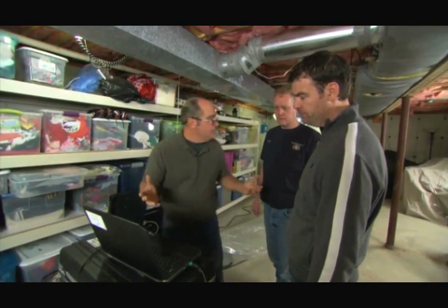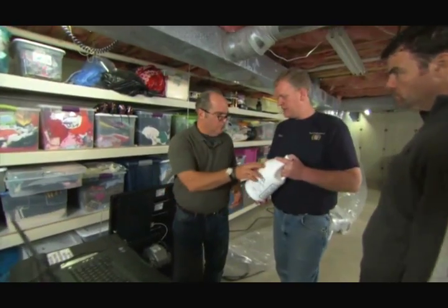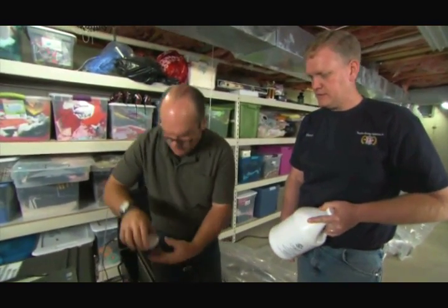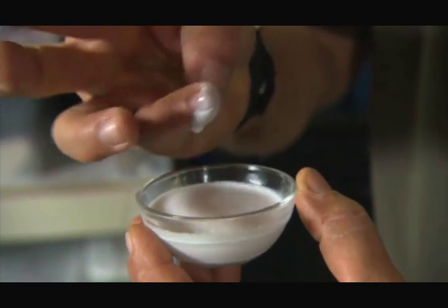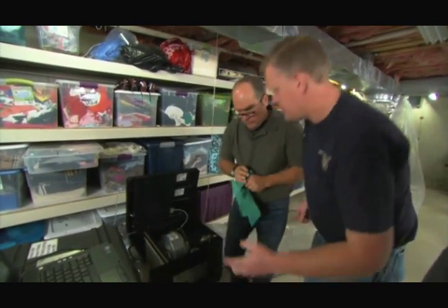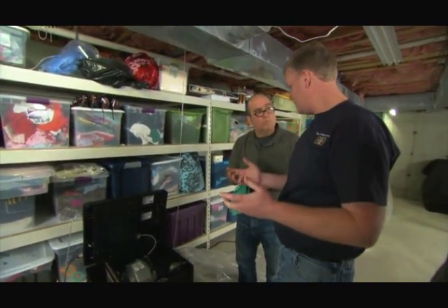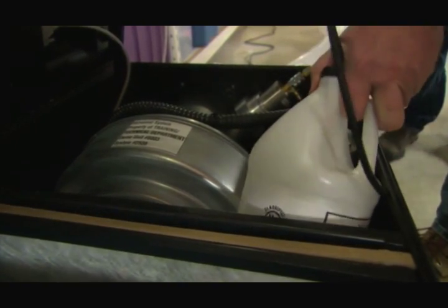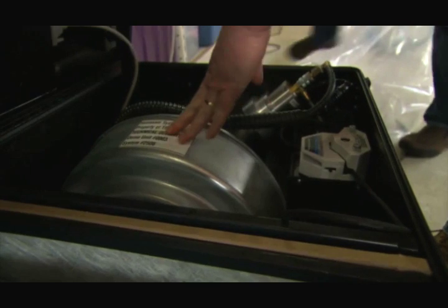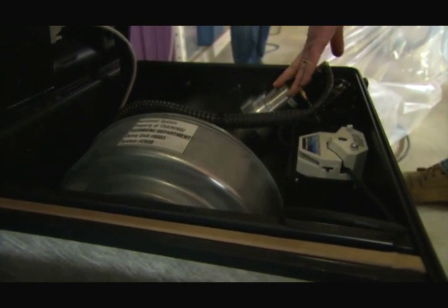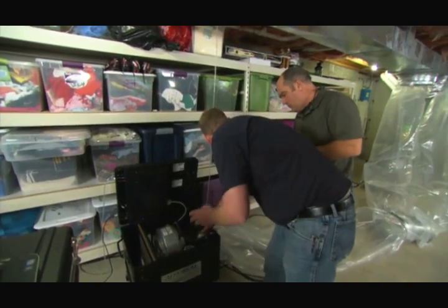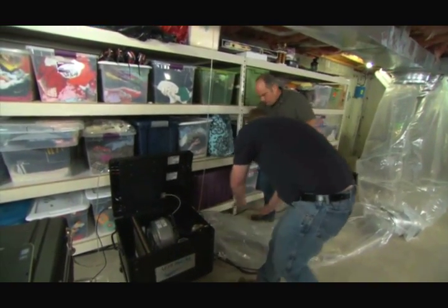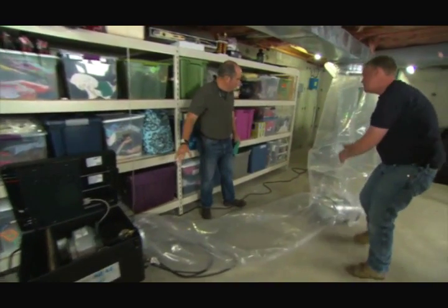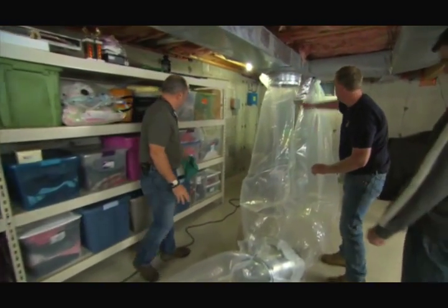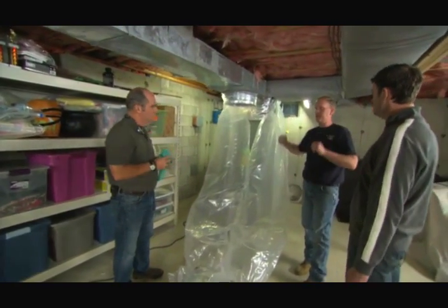It's unbelievable. All right, so how do you seal the ducts? Well, first we're going to start with the sealant. So that's a liquid. Is that what this is here? It is. Sort of milky, sort of rubbery. Great. How do you get it into the ductwork? It's a liquid. So in order to seal the ducts, we need to do it as an aerosol. So we're going to use this sealant. We use the same fan that we used for the pre-test. We have a nozzle that injects the liquid into the duct. The small particles that are now in aerosol travel through this flexible duct here to a Y branch. Then it can go to the return and the supply, and we seal both at the same time.